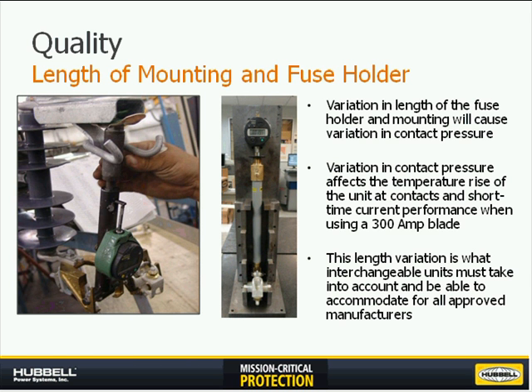This gauge length is 100% checked on all Chance units in production. Every cutout coming off the line, before grease is applied to the top contact, has this gauge tool put in it in both our Juarez and Wuhu plants. This is based on studies we've done with other manufacturers to ensure that the variation in fuse holder length will accommodate the mounting length. On the right photo you'll see a gauge checking the length of the fuse holder — just like the mounting, this is critical for our fuse holder to maintain continuous current operation and momentary ratings when using a 300 amp blade.